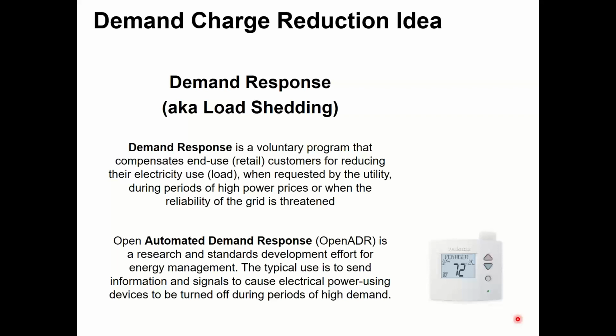One way that demand charges are reduced is what's called load shedding, or nowadays we typically call it demand response. We called it load shedding back in the 90s when I started. For some reason, that name evolved away. There's different ways to do that, like on chiller plants and things like that.